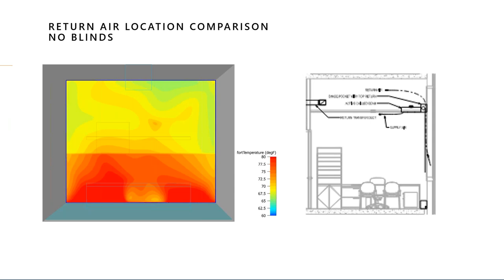This graphic on the right is a little bit hard to read, but the bottom line is that we had holes drilled in the shade pocket that was right against the wall. And so if you pulled that shade down, it would capture some of that solar heat and it would radiate into the ceiling plenum and get treated back at the air handling unit. And we tried to calculate, not super successfully, quite frankly, exactly what we were bypassing and what we were doing to not have to have the chilled beam deal with it. I think in the end, it was probably a 20% to 25% benefit for the chilled beam sizing.